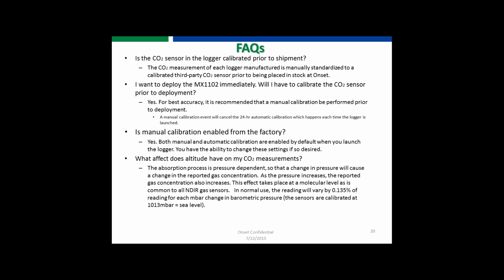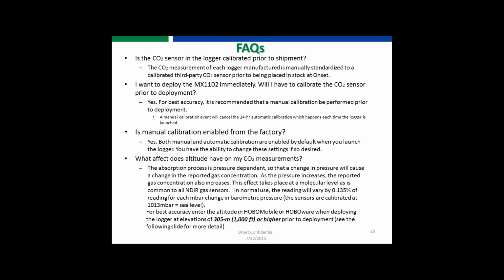The bottom line, or the rule of thumb that we're telling people, is if you're deploying the logger above 1,000 feet or above 305 meters, go in and put in your altitude, and that will help compensate for that change. Otherwise, your data may not be as accurate as it should be. Below 1,000 feet it really doesn't make a whole lot of difference, but once you start getting above 1,000, it does make a difference. And the higher you go, the more of a difference it makes.